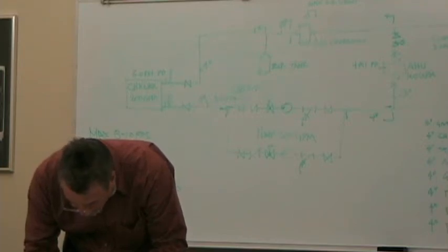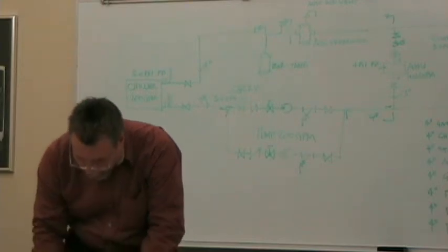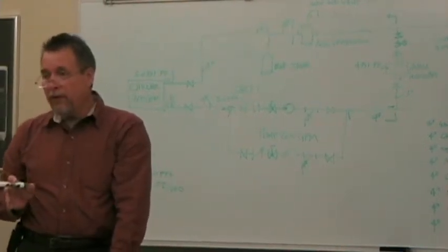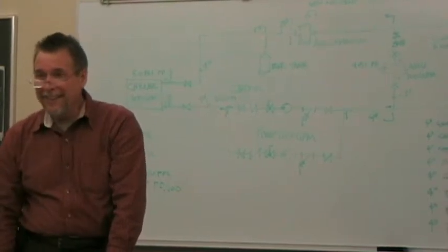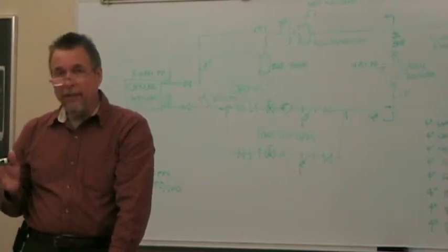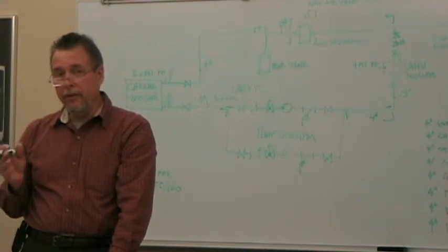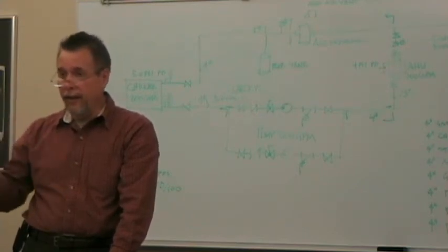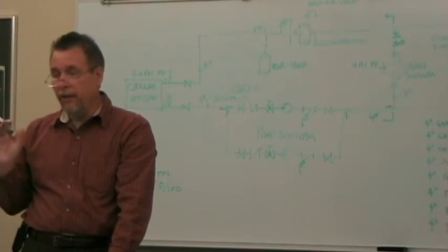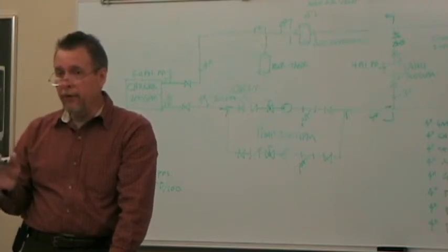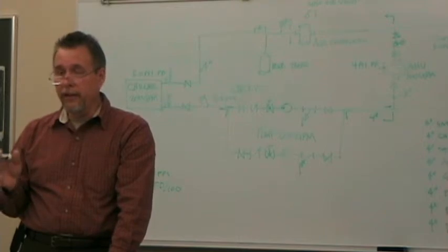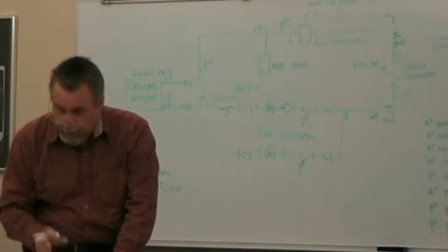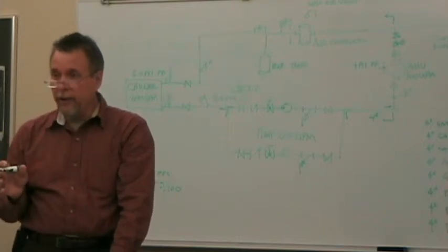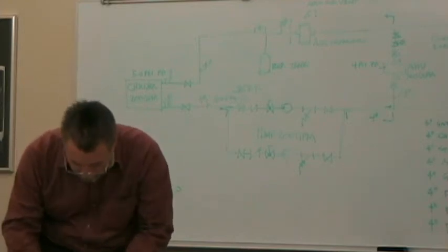How often did you run across, when you designed the system and then the contractor was out there, that it turned into a nightmare? Depends on how well you designed the system. If you knew what was going on and you took into account all the ductwork, the conduit, the cable trays, and you laid out your piping system with some experience and knowledge, then you got it very close. But yeah, there's always going to be some additional elbows, and I'll tell you how I took care of that.